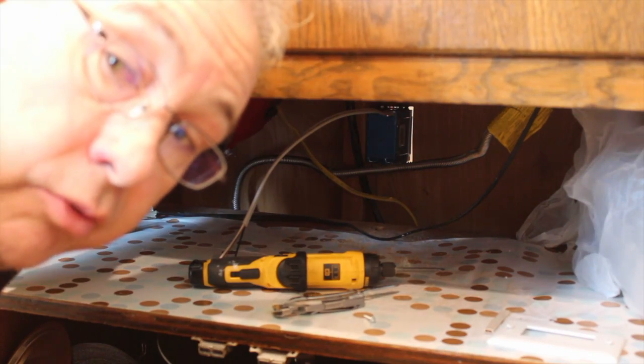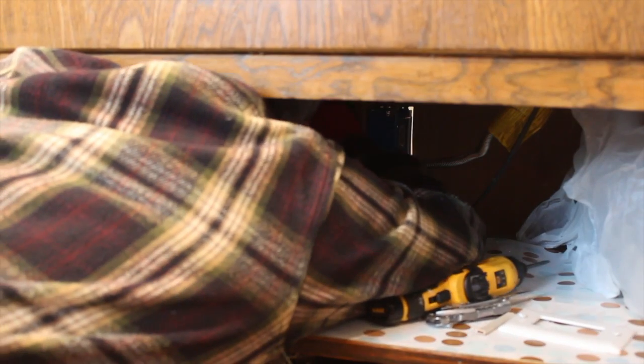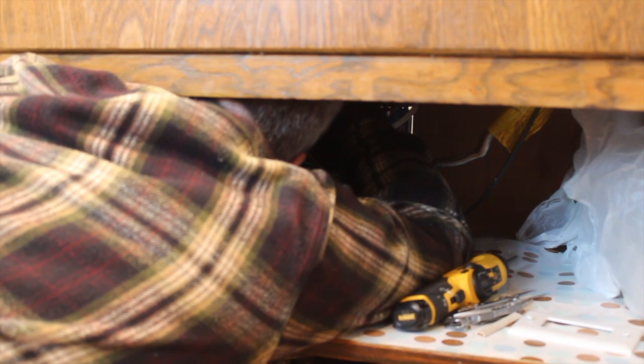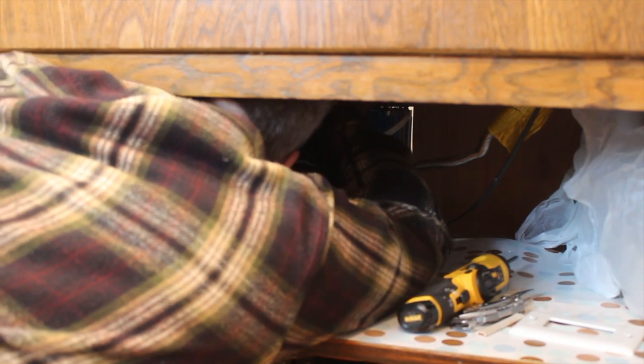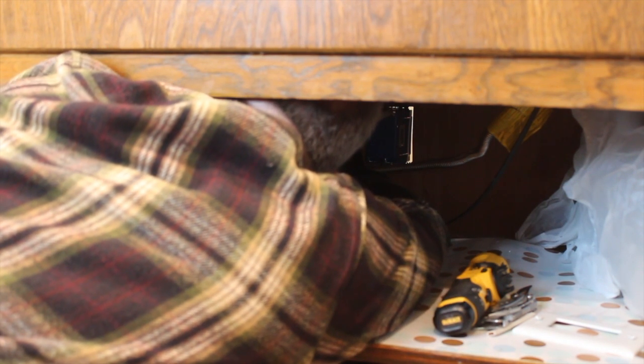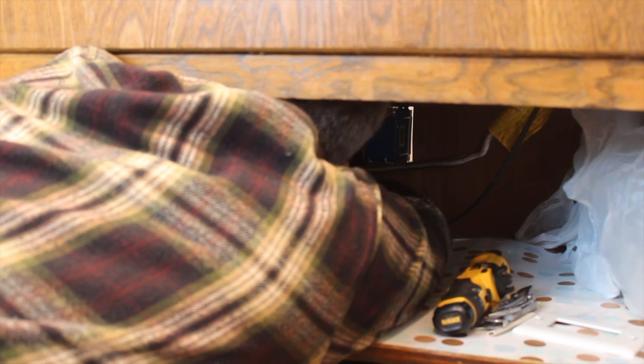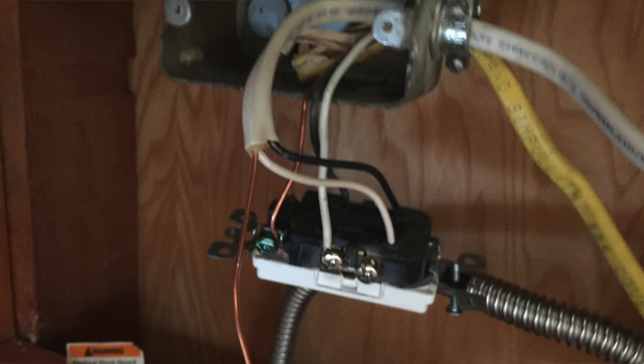It's the same kind of outlet, it's got those little holes you can insert the wires into, so it'll make this part really easy. I got to run the wire through this strain relief back here on the side of the box. The wire has to come through that and that prevents the wire from being pulled out by accident. I have to put my whole body in again, two arms necessary.